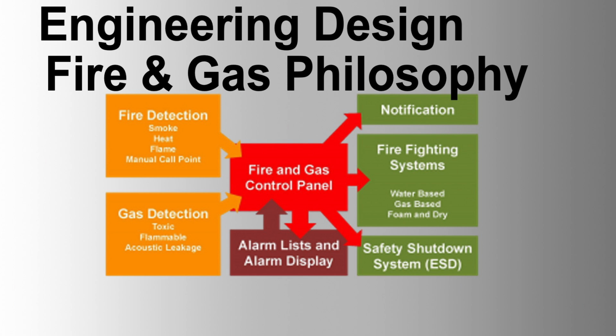Fire and gas system design philosophy. The fire and gas detection and protection system aims to provide early warning of fire or gas events in plant areas and buildings. It automatically initiates actions like tripping HVAC systems, closing fire dampers, and activating fire protection systems. Independent fire and gas systems are provided for central processing facility process, utilities, oil well clusters, and remote wells. The systems are SIL 3 rated Safety PLCs designed per IEC 61511 and IEC 61508 Part 2, meeting hardware fault tolerance HFT requirements based on safe failure fraction SFF value specified in IEC 61508.